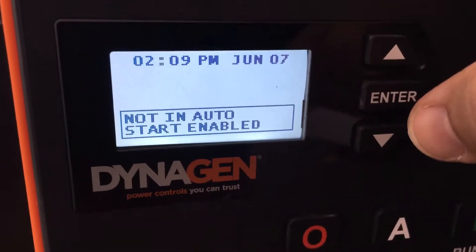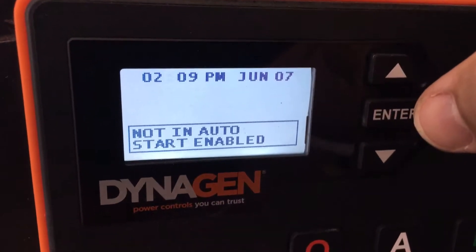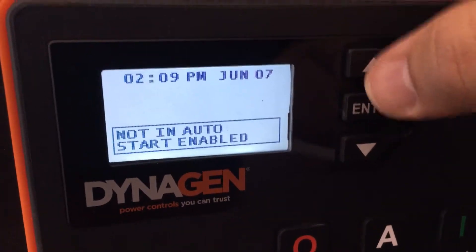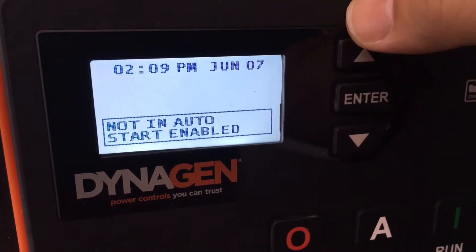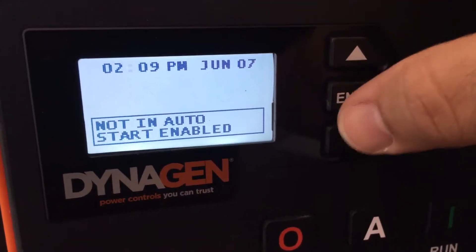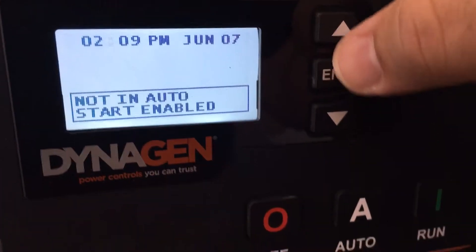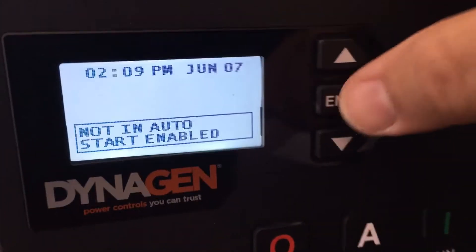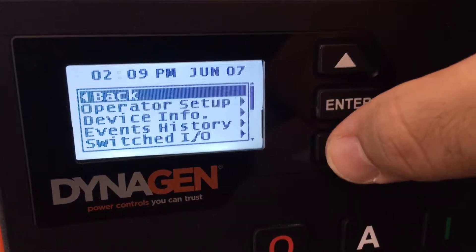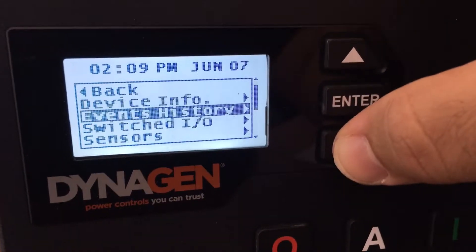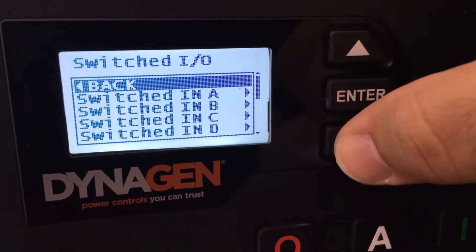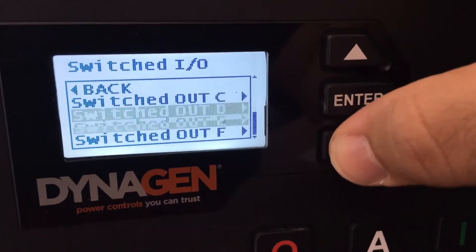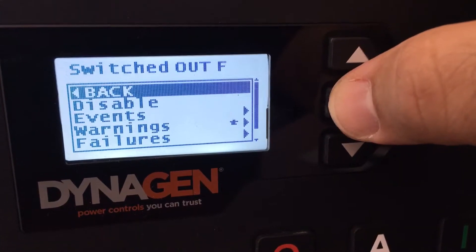There are two outputs available on the controller that you can use to switch something on and off. To switch a relay or light on and off based on low fuel level or high fuel level, we'll do the following. Press enter, go to switched output. You have two available you can use: Output E and Output F.